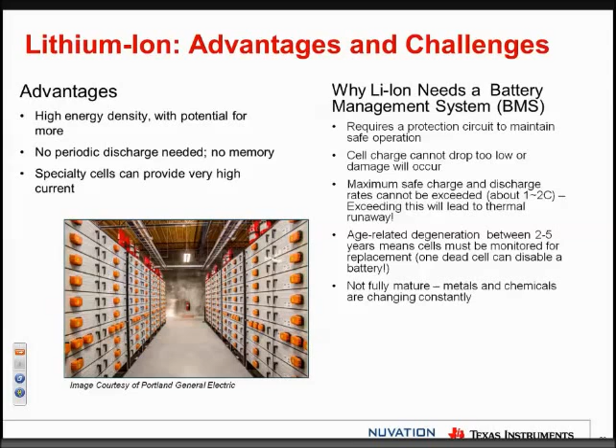A challenge with lithium, though, is how closely it has to be monitored and controlled. In a typical grid application you may have thousands of cells to get the capacity you need, and each cell needs to be monitored and controlled so it stays within its voltage and current specification. If you go outside of those limits too far or for too long, you'll either damage the cell or heat it up and lead to thermal runaway—you might get a fire starting. So it really requires a battery management system connected to the battery to ensure everything operates safely.